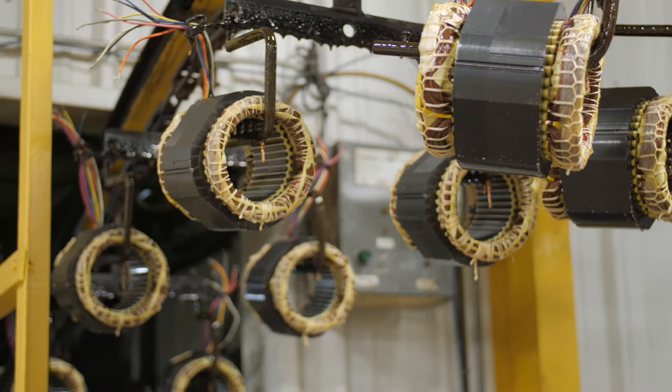The key requirements include: power ratings 1 through 500 horsepower, NEMA premium efficiency, inverter duty, single voltage, three leads only, Class 1 Division 2 atmosphere, T3 temperature code, all cast iron construction, IP55 without the use of contacting seals, temperature limits for wiring and bearings, strict vibration and noise limits, and an IEEE 841 test report shipped with each motor to ensure it meets all criteria.